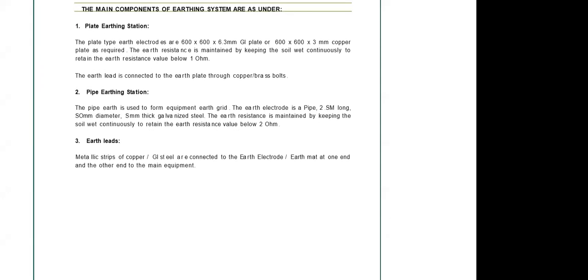Like plate earthing, another type is also available, that is pipe earthing. This is basically a porous pipe that is embedded into the soil or the earth, and charcoal and other chemicals are added to it, and then this earthing is done. This is also equally popular. It depends on the application and what space constraint we have. Earth leads are basically metallic strips from this plate earthing or pipe earthing, going to the respective equipment. That is, through those strips it is laid.